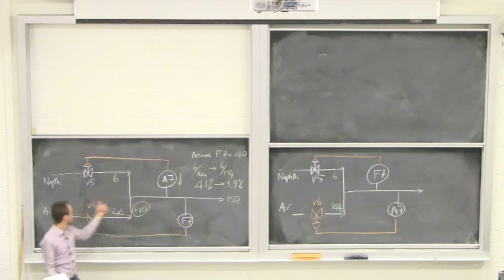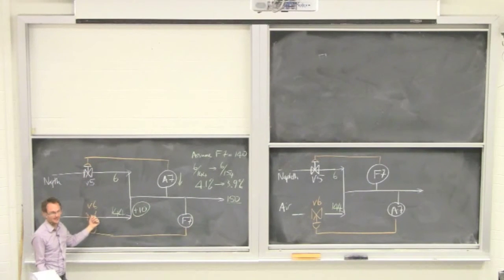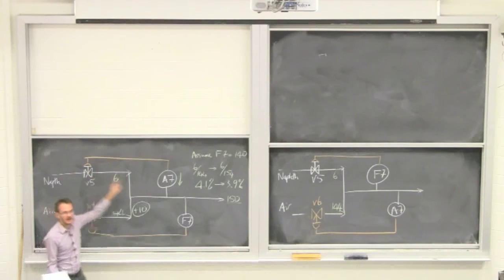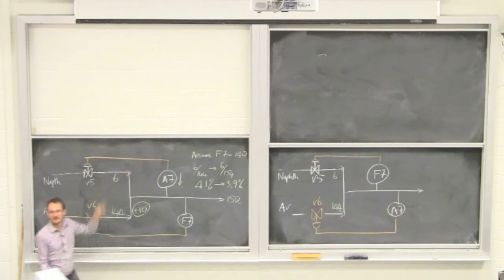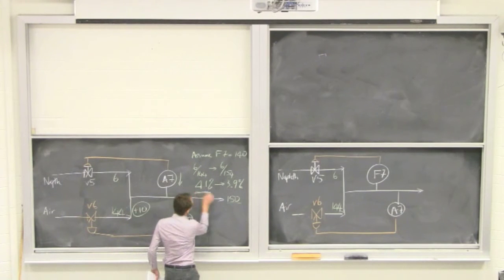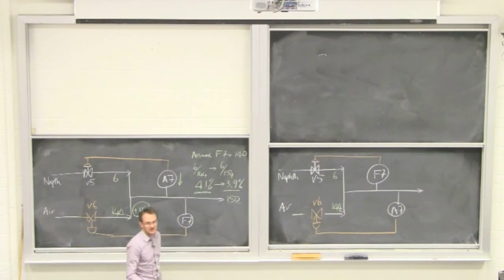Flow gets affected and changes its valve. When that valve changes for V6, it affects A7. A7, it changes V5, and you just keep doing that sort of cycle around. We looked at this in at least the students I taught for 3P. I know I showed you that diagram, how the information snakes around the block diagram. Okay? So the control loops interact. That's the terminology we use. But the interaction here is fairly minor. So you affect one loop, but by a small amount.